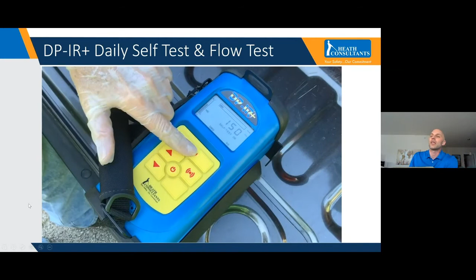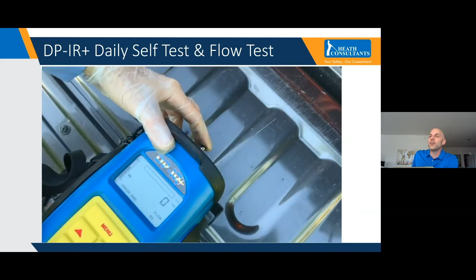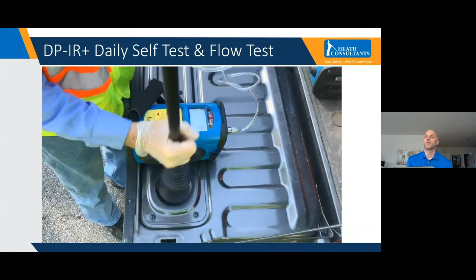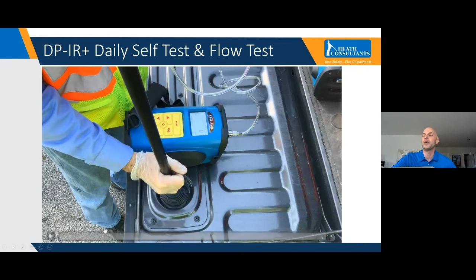Generally, we recommend that once the daily self-test is finished, you also do a flow block test. What you're doing here is making sure there are no leaks from your point of inlet to the exhaust of the instrument. You can see here Roy covered the instrument up and then blocked the probe once he had it on there.